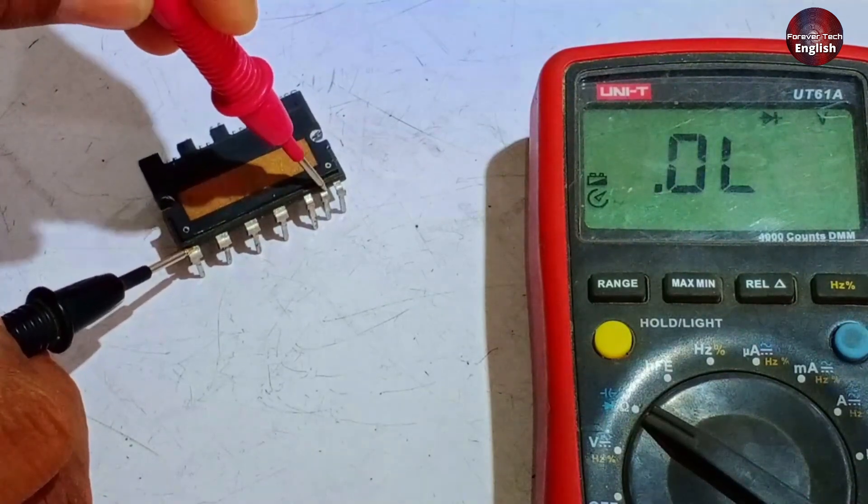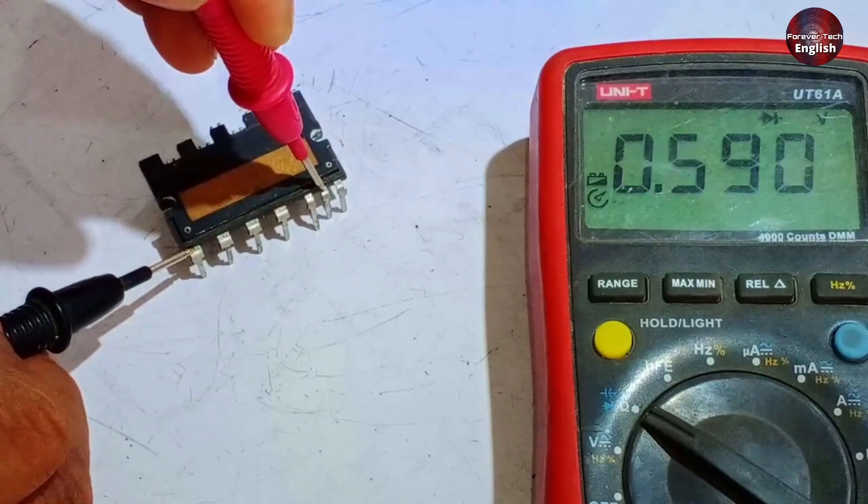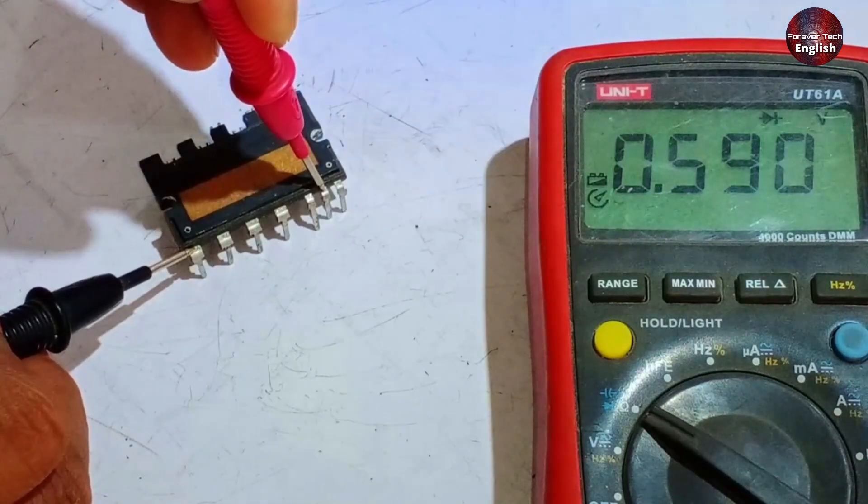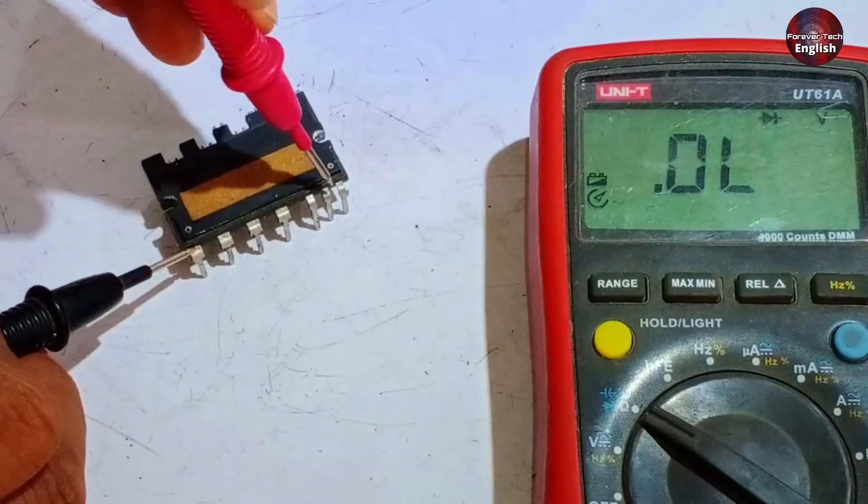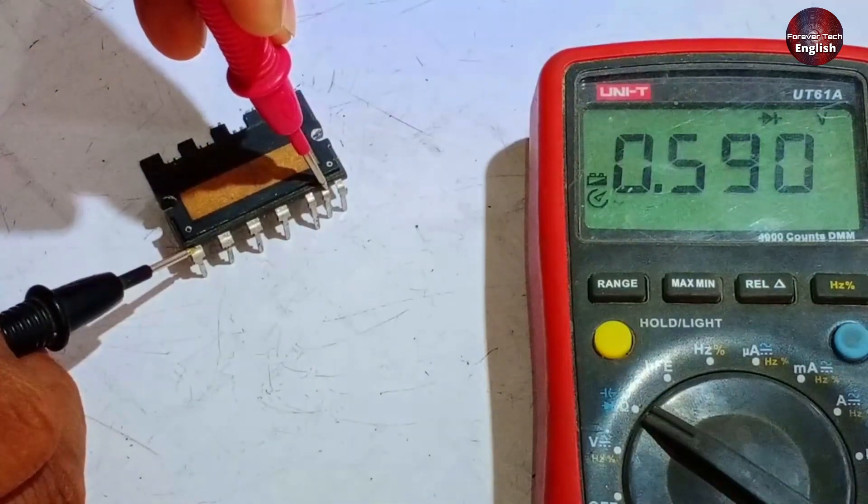Next, we'll check pin 22. There shouldn't be any value displayed here, but it's showing value here. Now, what's the situation here? Both IGBTs have shorted, which is why a value is appearing here, but otherwise, this value wouldn't show.